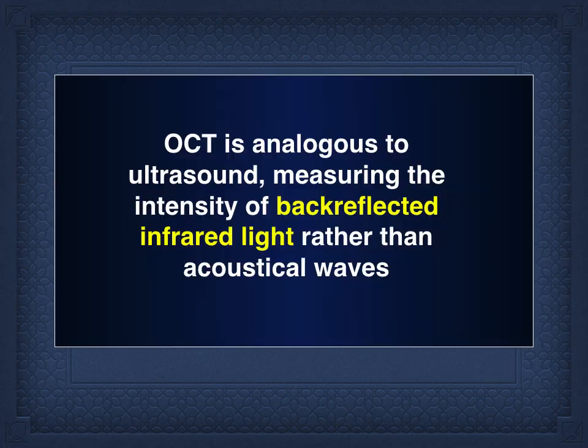Going back to the superficial explanation we used in part one, OCT is analogous to ultrasound measuring the intensity of back-reflected infrared light rather than acoustical waves. In this presentation, we're going to look at the limitations of that definition because we're not actually measuring the back-reflection of light. We're measuring the interferogram between the sample arm and the reference arm.